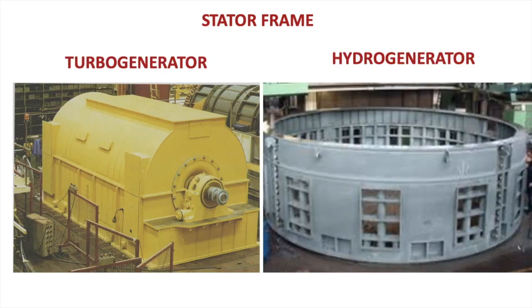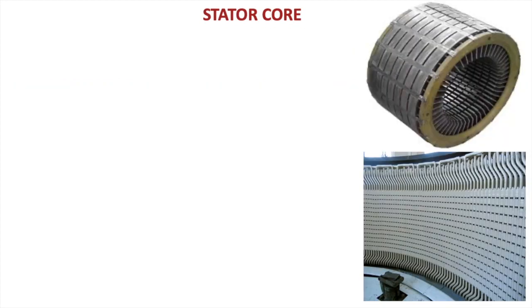Now here you can see the frame of a large turbo generator and a large hydro generator. Normally you can see that the turbo generators are placed axially while hydro generators are placed vertically. Next comes the stator core. The top one is the core of the turbo generator while the bottom one is the core of the hydro generator.